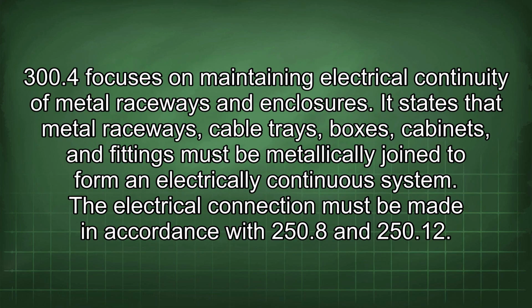300.4 focuses on maintaining electrical continuity of metal raceways and enclosures. It states that metal raceways, cable trays, boxes, cabinets, and fittings must be metallically joined to form an electrically continuous system. The electrical connection must be made in accordance with 250.8 and 250.12.